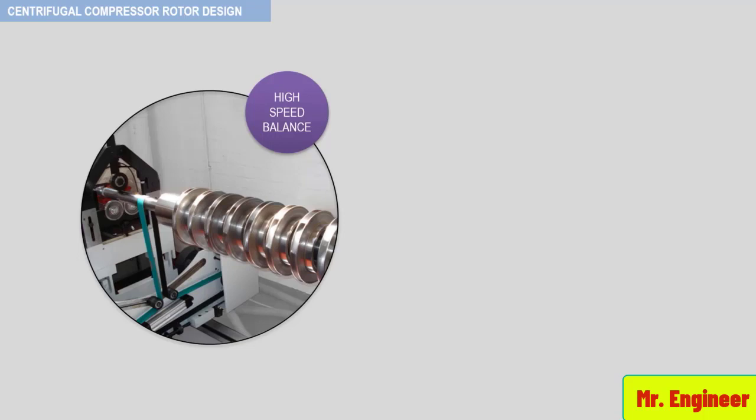So that you are aware, over the last 10 to 15 years, high-speed rotor balance has been popular. High-speed balance procedures were originally designed for highly sensitive rotors with low values of rotor stiffness that had a history of field vibration problems. High-speed balance machines have the capability of balancing the rotor at rated speed. This is done by operating in a vacuum and providing sufficient power to operate at this speed.